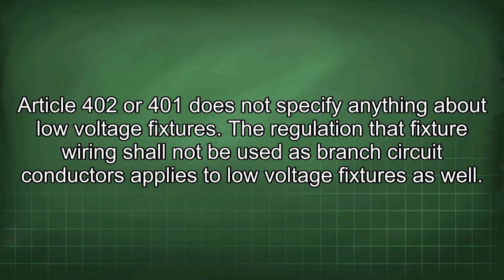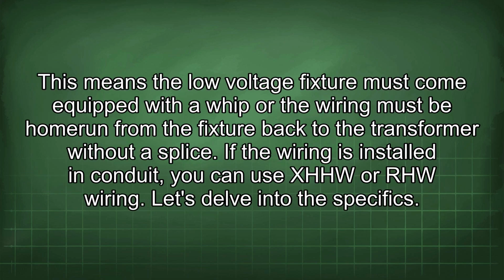Article 402 or 401 does not specify anything about low-voltage fixtures. The regulation that fixture wiring shall not be used as branch circuit conductors applies to low-voltage fixtures as well. This means the low-voltage fixture must come equipped with a whip, or the wiring must be home run from the fixture back to the transformer without a splice. If the wiring is installed in conduit, you can use XHHW or RHW wiring. Let's delve into the specifics.